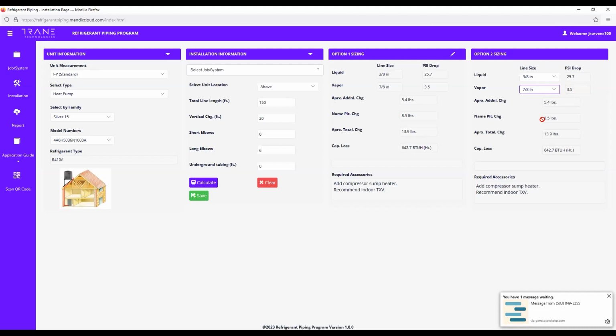Okay. So this works for all the equipment. The only thing you want to be careful of is variable speed. Use the variable speed charts that are in the variable speed manual. Double check this program with that before you just go by this program on variable speed. Okay, so there's certain units that you can't use certain sizes with for variable speed. So just make sure that you're looking at it. Anybody have any questions on the piping program?